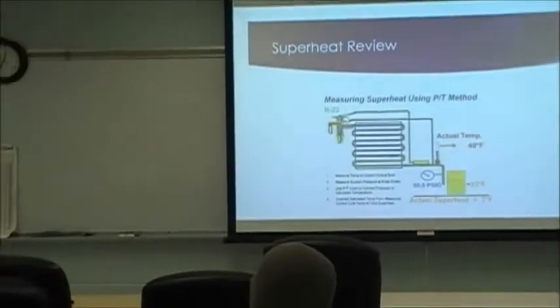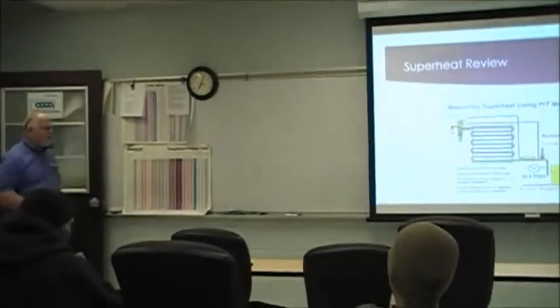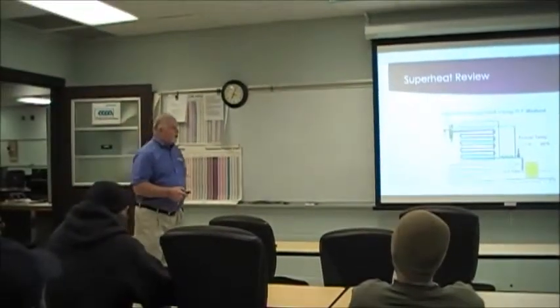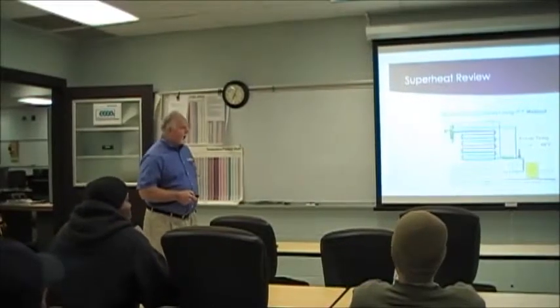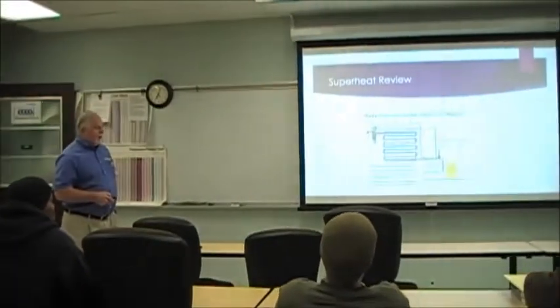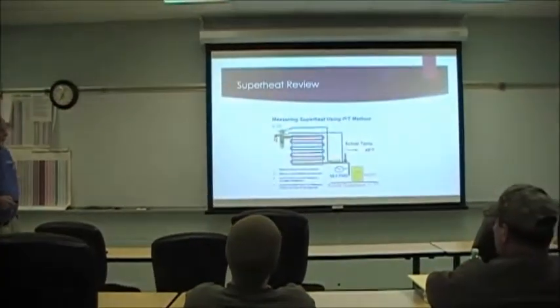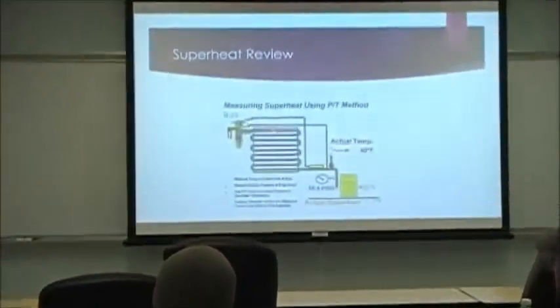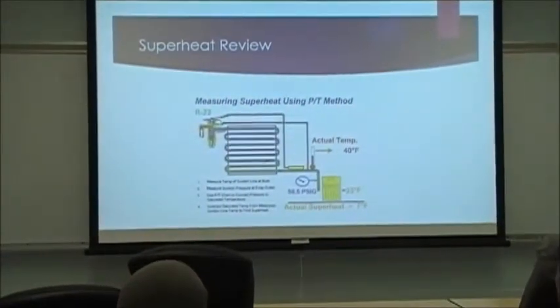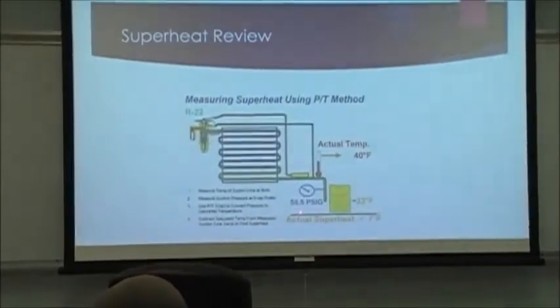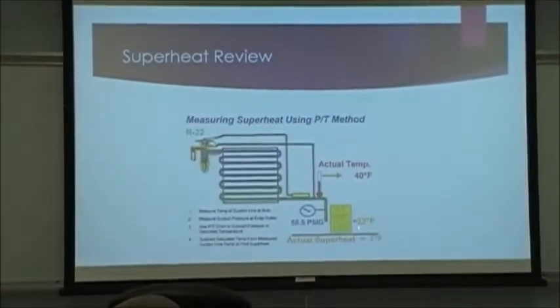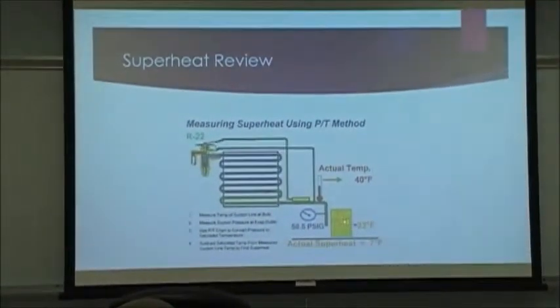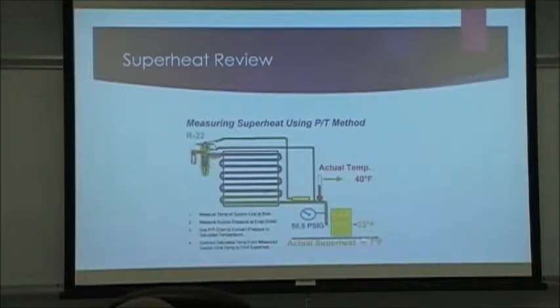That happens with any refrigerant we have, it works with any refrigerant. So we take this refrigerant, this vapor and liquid, and boil it off. Now that coil temperature, what is it? At 58.5 pounds, 33 degrees. It's right there in those letters. I know you can't read that temperature chart, but let's just assume it's real and correct.